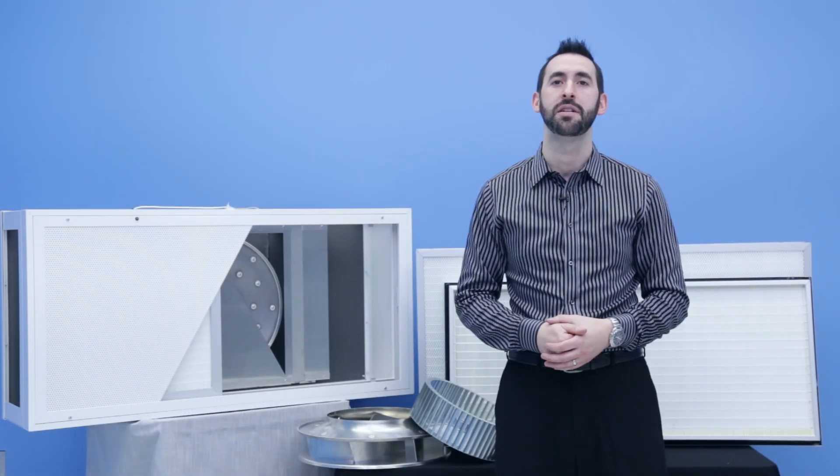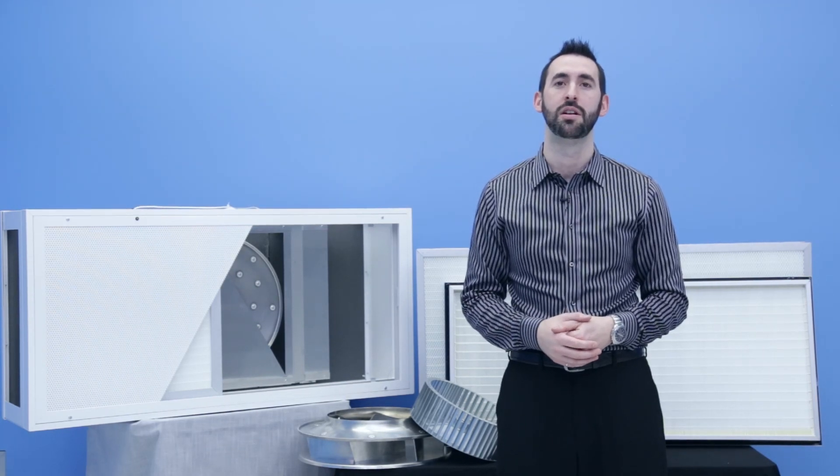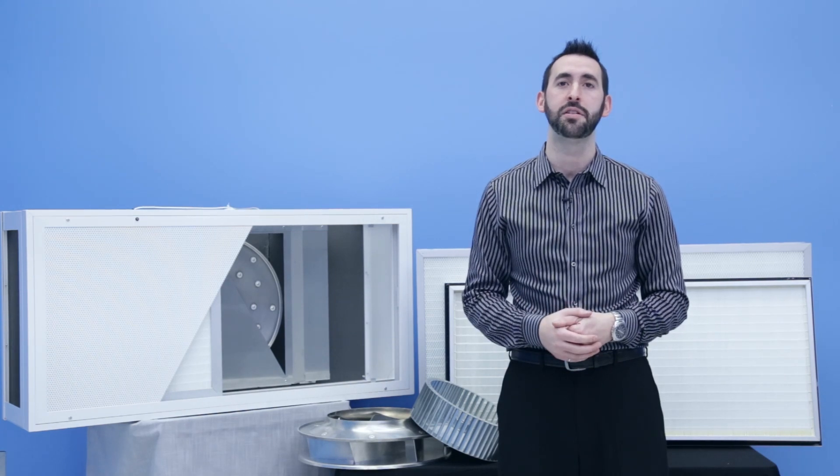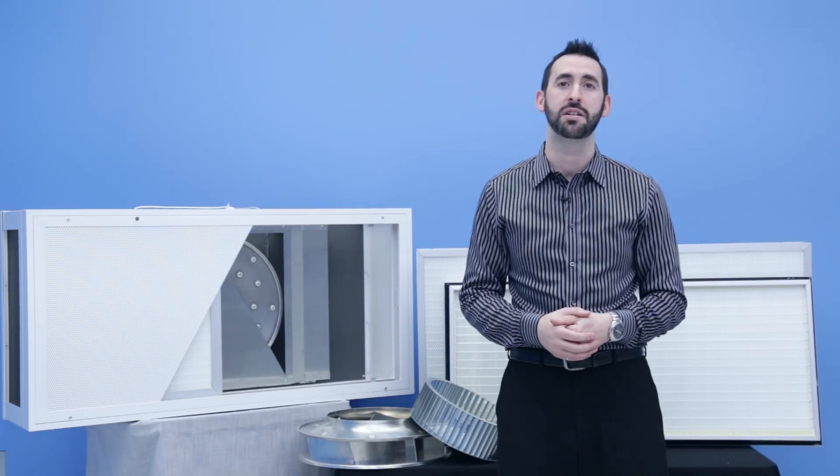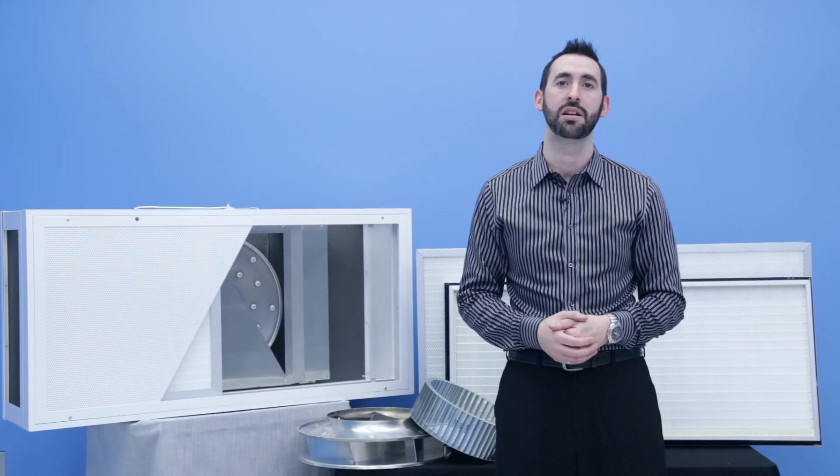When using an ECM there are two available motor programs, the first of which is constant flow. The constant flow motor program maintains the airflow through the fan filter unit independent of the static pressure as the filter loads. This is ideal for negative pressure common plenum designs.